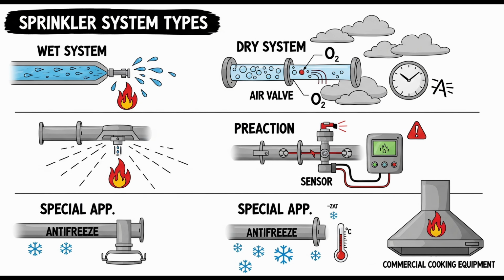Good isolation. And if a compressor is the dedicated air supply, its electrical installation must comply with safety standards, specifically NFPA 70, the National Electrical Code, Article 430, which covers motors and compressors. Standard electrical safety. Now, how is the actual required system air pressure determined? How much pressure do you need? It must be maintained either according to the dry pipe valve manufacturer's specific instruction sheet, they know their valve best, or, if that's not available or specified, it must be 20 psi above the calculated trip pressure of the valve. Trip pressure, what's that?